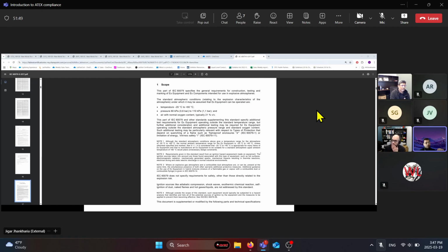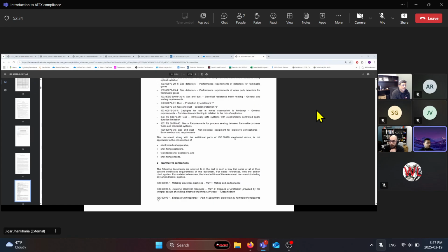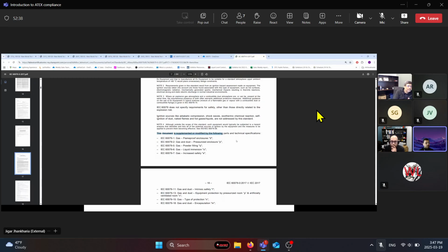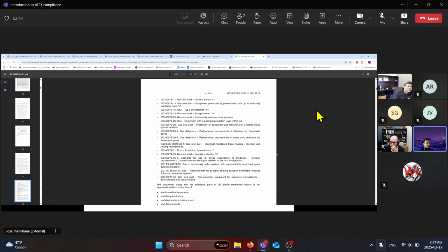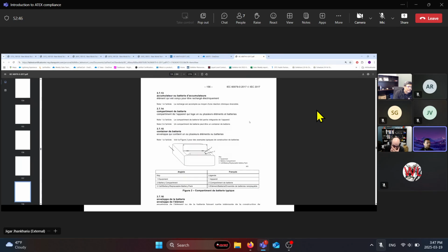So for -7, yes, the minimum IP rating requirement for the equipment is 54, and that includes whether it's a tool, an enclosure, or anything like that. For example, if you enclose your product in an enclosure, it has to be sealed so that no dust or water can enter. And we can only do IP testing on an enclosed product. We can't do it on an open-ended product because for sure it's going to fail. So there has to be some sort of enclosure for us to test the product. If that makes sense. Understood. Yeah. So this standard references, and is supplemented or modified by, the following parts. It goes back to all the different methods of protection, and then in the appendix there are various tables you can look at. Sorry, I reached the French part.